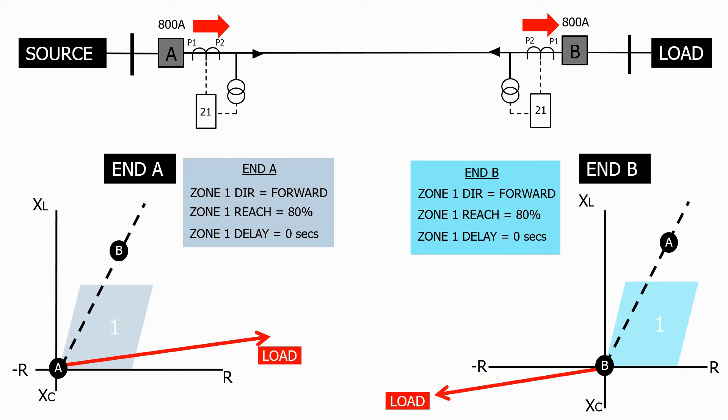Let's now add a fault halfway down the protected line. As this is a solid system, fault current now flows in from both ends of the feeder. The fault is at 50% of the line length and therefore it falls well within the zone 1 impedance characteristic for end A and end B.